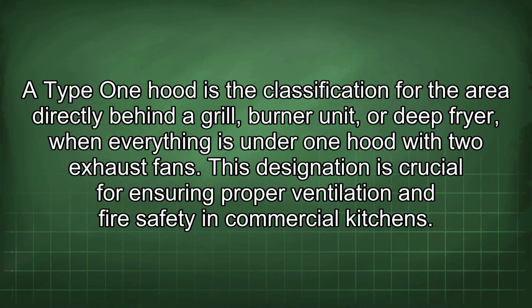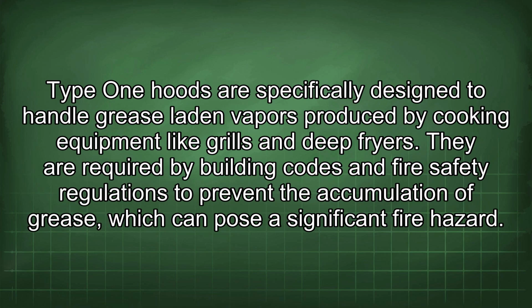Type 1 hood is the classification for the area directly behind a grill, burner unit, or deep fryer, when everything is under one hood with two exhaust fans. This designation is crucial for ensuring proper ventilation and fire safety in commercial kitchens. Type 1 hoods are specifically designed to handle grease-laden vapors produced by cooking equipment like grills and deep fryers.